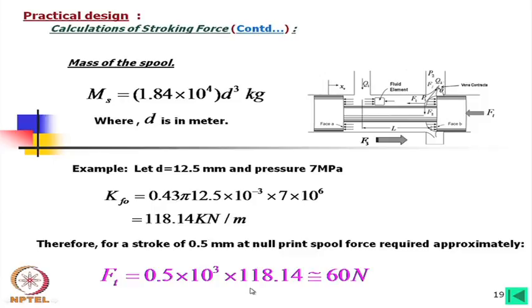For a 12.5 mm diameter spool at steady state, the required force is approximately 60 N, which is about 6 kg force. This is neither very small nor very large. Usually an electric drive — such as a solenoid or electrical torque motor — must generate this 60 N force. With this knowledge, today's lecture concludes, and we will continue this analysis in the next lecture.